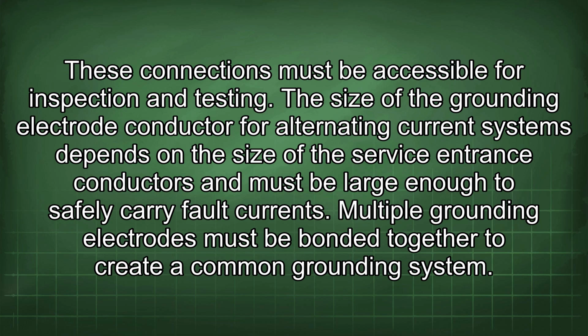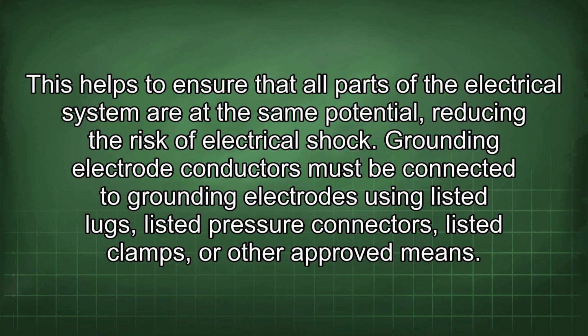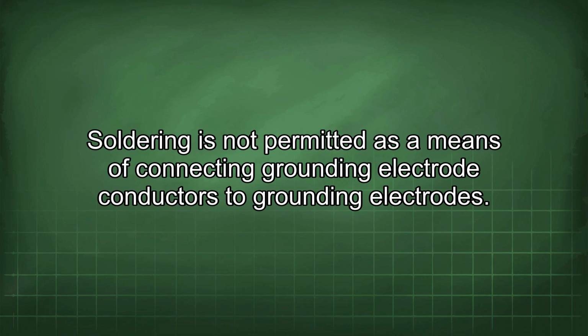Multiple grounding electrodes must be bonded together to create a common grounding system. This helps to ensure that all parts of the electrical system are at the same potential, reducing the risk of electrical shock. Grounding electrode conductors must be connected to grounding electrodes using listed lugs, listed pressure connectors, listed clamps, or other approved means. Soldering is not permitted as a means of connecting grounding electrode conductors to grounding electrodes.